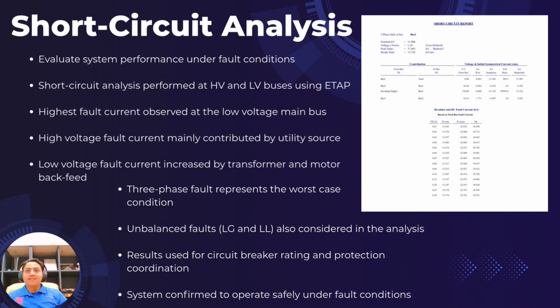For the short circuit analysis, we look at what happens when a fault occurs in the system. The purpose of this analysis is to make sure the equipment and the protection devices can handle fault conditions safely. From the results, we found that the highest fault current happened at the low voltage main bus. This is because the impedance on the low voltage side is lower, and there is also a contribution from the transformer and the motor. At the high voltage side, the fault current mainly comes from the utility supply.